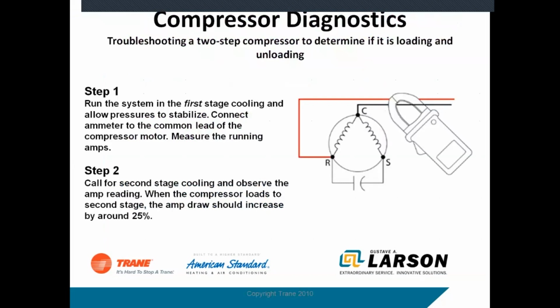So that's the basic, that's how all scroll compressors work. Now, if it's a single stage scroll compressor, it's just going to pump continuously. And like you said, there's a check valve in there. In the old recip compressors, which we'll get to, we used to use a set of valves, or actually reeds, little reed port valves. And that was also your check valve. In the scroll compressors, we don't have that. So somewhere in the system, there's usually a check valve.